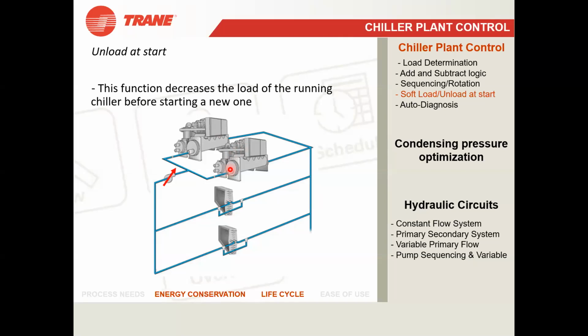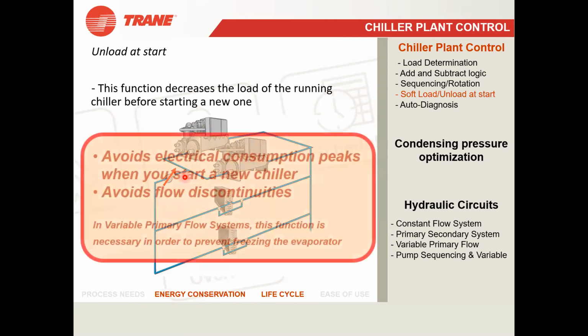I think it is like 180 to 360 seconds, maximum 360 seconds actually. So it reduces its load to minimum capacity, and then it switches on the pump and other accessories. Then electricity consumption will be very, very little, at least compared to starting the other chiller and accessories while the first chiller is at full load. So we are avoiding electrical consumption peaks when we start a new chiller. I want you all to understand these two points, soft load and unload at start.